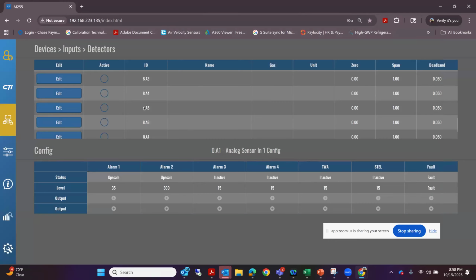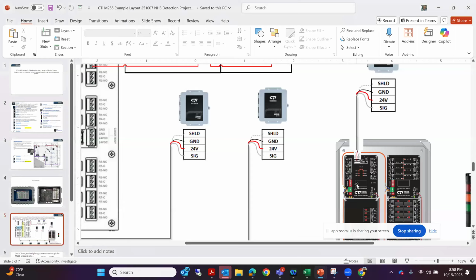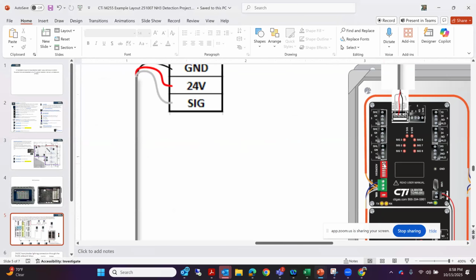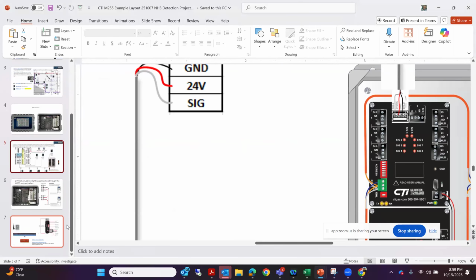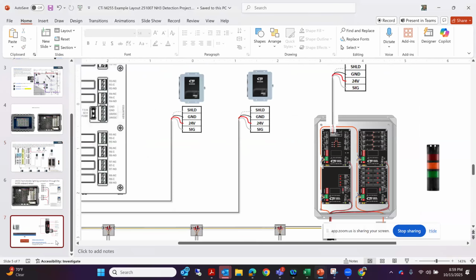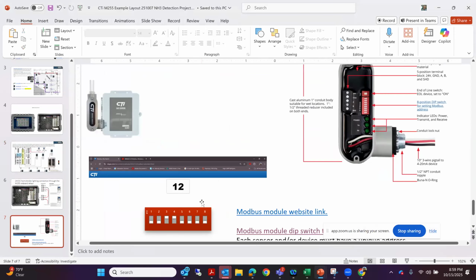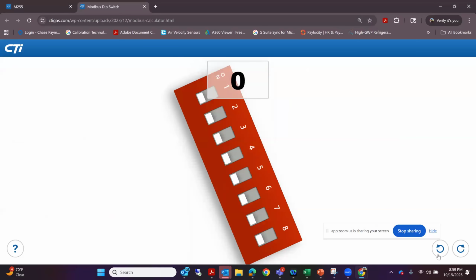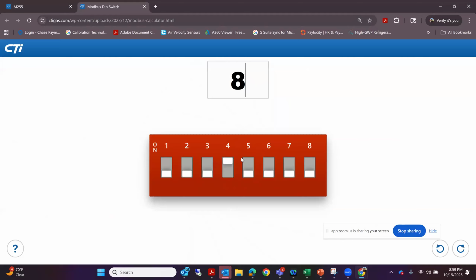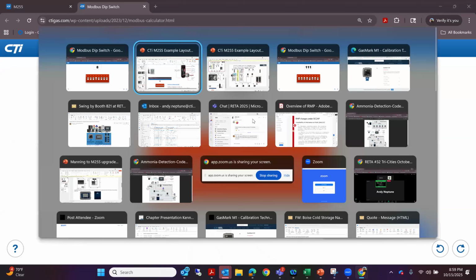And so when you look at that 8 right here, that 8 is going to be that dip switch. So that dip switch, if we go in there, that dip switch will be set for 8 or Modbus ID 8. So if we went in here and said, okay, what does 8 look like? I think we might be able to figure that one out, because 8, that should be what? Mine's a little rough, but I think we just go 2, 4. It would be just the 3 up, right? I can't remember. My discretes are so rough, I couldn't tell you what 8 looks like. I think it is just, okay, 4 up. So there's your 8. So that one would be addressed to 8, if your guys are getting that.